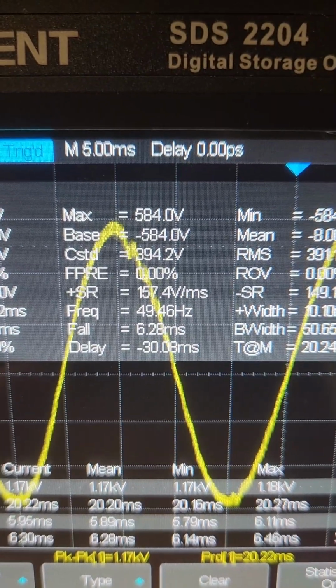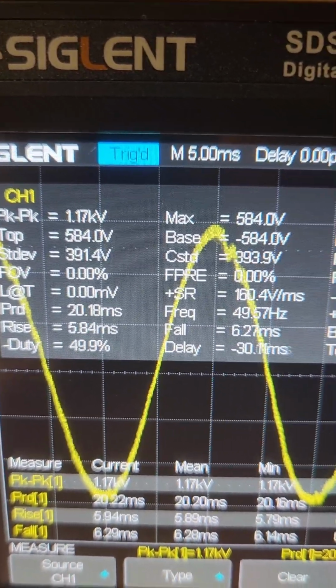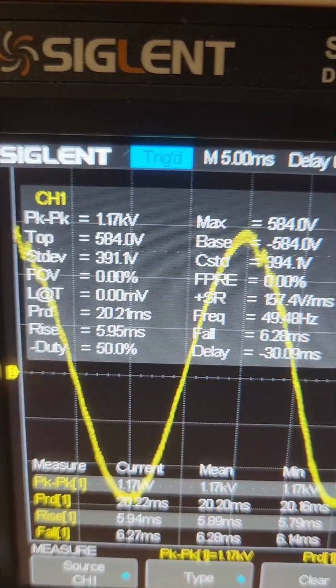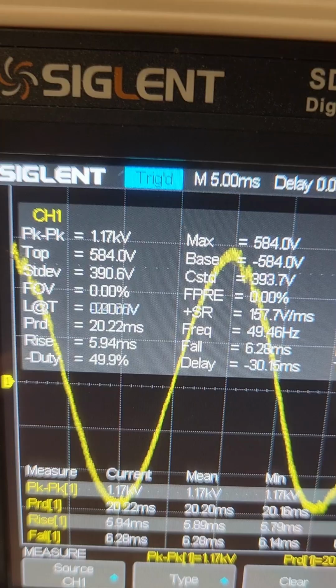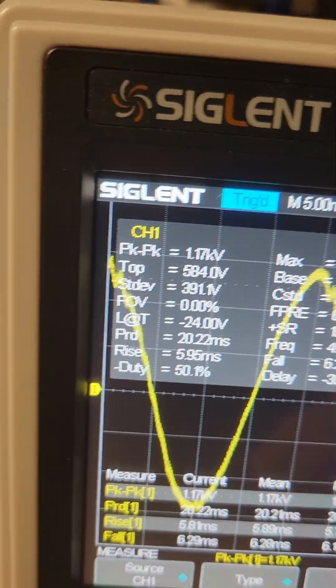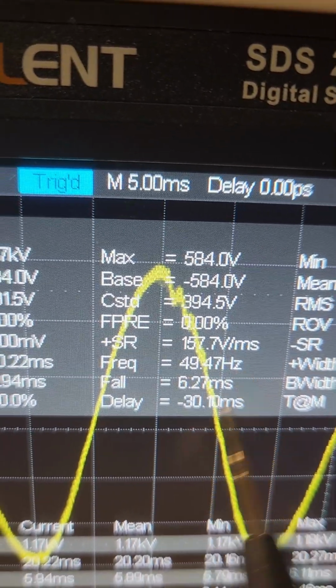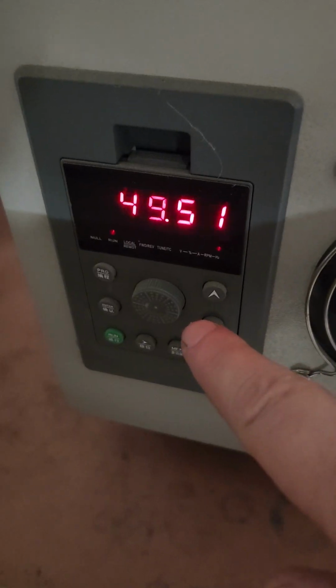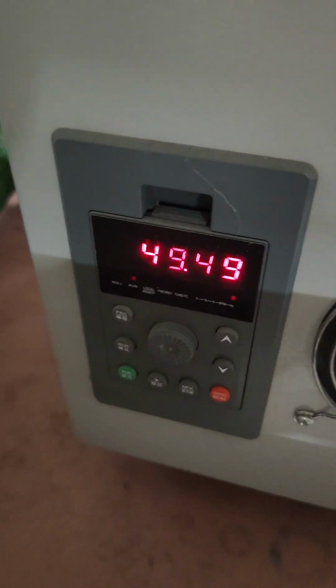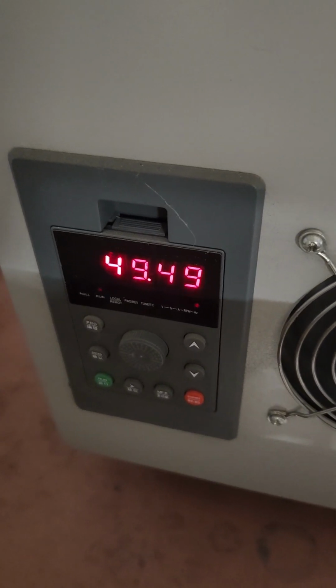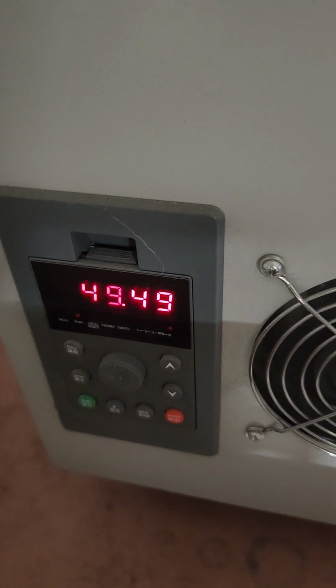This inverter is running a VF curve, voltage frequency. As the frequency increases to the nominal frequency, about 49 point something, the voltage increases too. At 50 hertz you have the programmed voltage. I can adjust that from here by turning this knob, but if I go higher the voltage goes higher, and if I go lower, which I'd like for lower voltage, then the frequency isn't 50 hertz anymore.